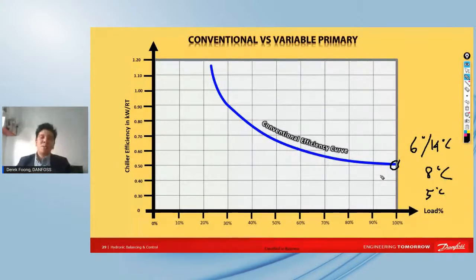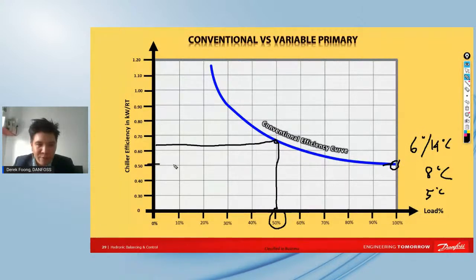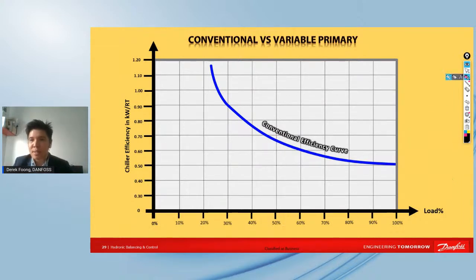And this is where I would say if the system is operating on full load, this is going to consume, okay, about 0.5 kilowatt per ton, right? And this is going to consume about 0.65 kilowatt per ton at 50% load, for instance. And now we see a surge of 30% higher energy consumption at 50% load. So this is one of the typical curves, but many manufacturers might have different curves. But what we know is that systems don't always run at full load all the time. Systems run at part load 90% of the time.